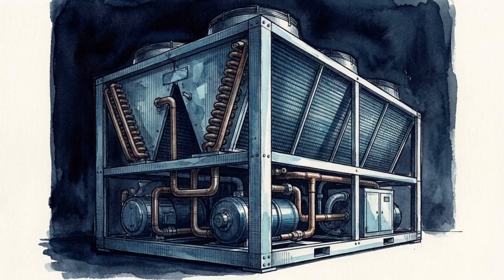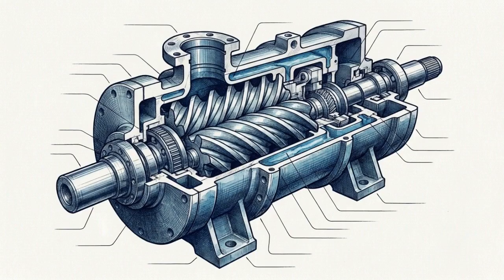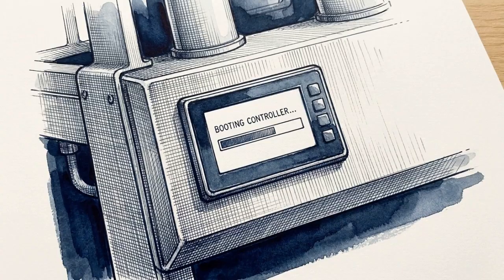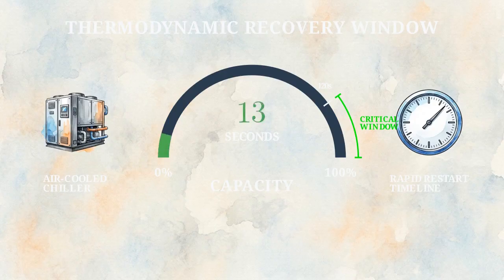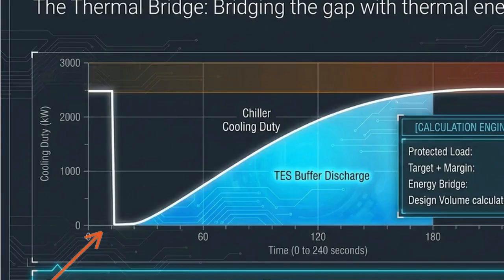Air-cooled chillers are heavy and highly complex machines. They are bound by physical limitations like the rotational inertia of massive compressors and the required boot-up time for their onboard logic controllers. To safely navigate these mechanical thresholds and return to 100% capacity, an air-cooled chiller requires between 120 to 180 seconds. At T0, the white cooling duty line plummets to 0.